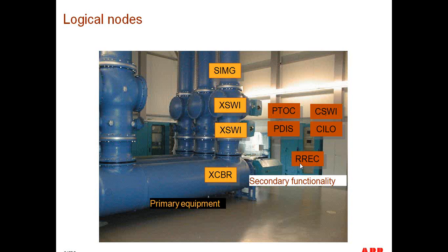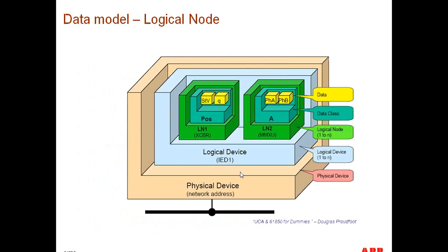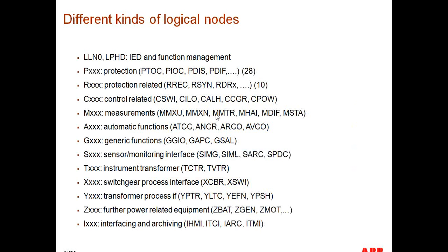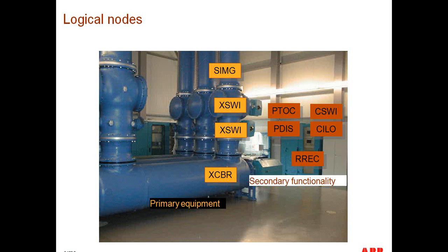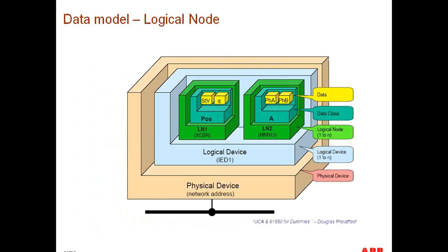and auto reclosing. And with multi-function microprocessor protection devices, the idea is that a single device could house all of these different functions. So if we just look back for a second and we see here this physical device, again, this physical device could be your SEL 421 or your REL 670. And then inside of it, there's going to be several of these boxes or several of these logical nodes which make up the functionality of the relay.